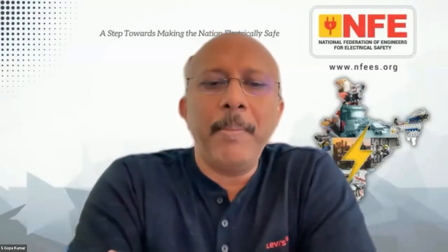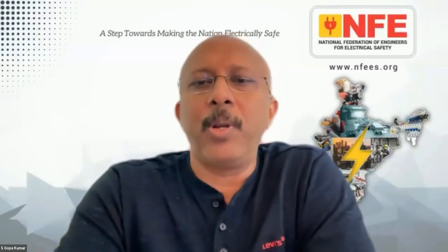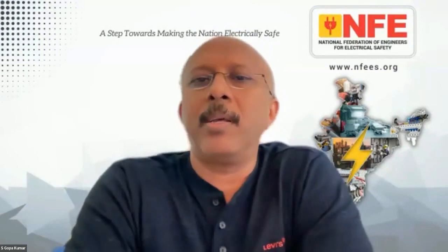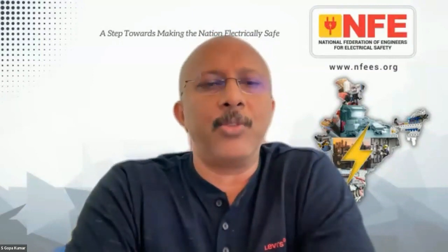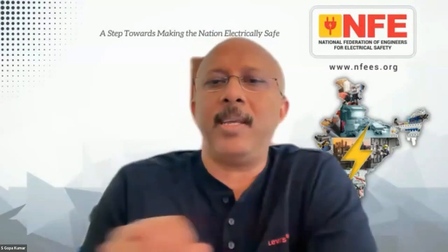Like Paul said, it's only if it creates an even more low impedance path, but generally I don't see that happening. So the point is the equipotential bonding creates the equipotential zone, and it has to go back to the source, which is the transformer, and that's what the protective earthing is for. Actually, the supplementary equipotential bonding's main purpose is to reduce the touch voltage. So it's not for taking the fault current. That is what is defined so far in these standards.